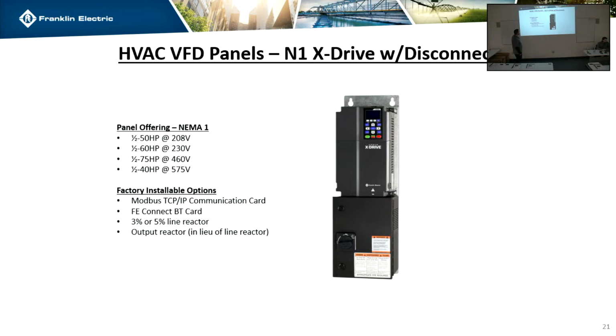The only thing that's different is for our NEMA 1 offerings, they have the FE Connect Bluetooth card, like we talked about earlier. And then they all also come with a 5% line reactor as a standard. So the only options that you really have for those would be the Modbus TCP IP card, if you want to add that, or an output reactor or output filter, depending on what the distance is from the drive to the motor. That's really what the determining factor would be for those. Typically, they're not really needed for HVAC applications because usually the motor is going to be pretty close to the drive. But there are those odd circumstances where it could be maybe a couple hundred feet or something like that, where we'd recommend having a reactor on the output side of it.